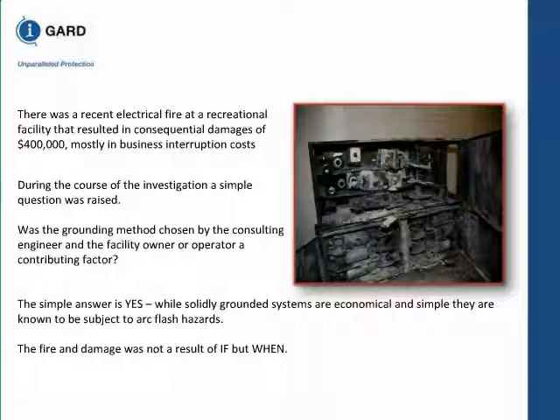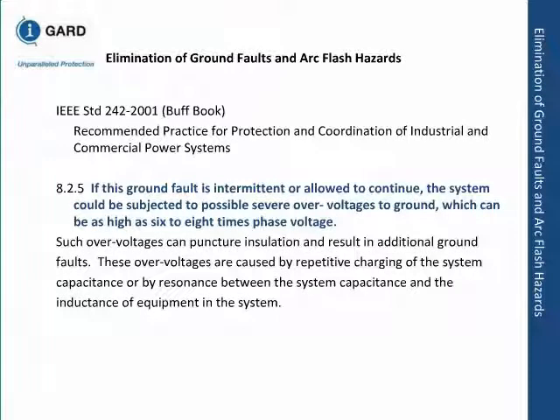A resistance grounded system prevents your equipment from having damage from arcing faults. Some other reference from an IEEE standard. This is for a delta ungrounded system. If the ground fault is intermittent, because it's sparking and allowed to continue, the system could be subjected to severe voltage, which can be 6 to 8 times normal. Now, how did we come up with 6 to 8 times? In theory, they can go forever. But at 6 to 8 times, other equipment will be damaged and the fault will clear. So you can see the ungrounded system has a lot of transient problems.